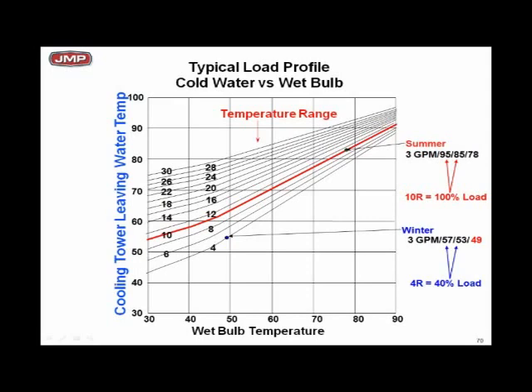How do you size your cooling towers? How much cooling you're going to get out of that cooling tower at 50 degree dry bulb and 45 degree wet bulb. If I slide under 45 degree wet bulb, I think you see 45 degree wet bulb making about 60 degree water. So I'm really looking at about a 15 degree approach on that same tower, same load, double the approach, same tower by lowering the wet bulb to 45 degrees.